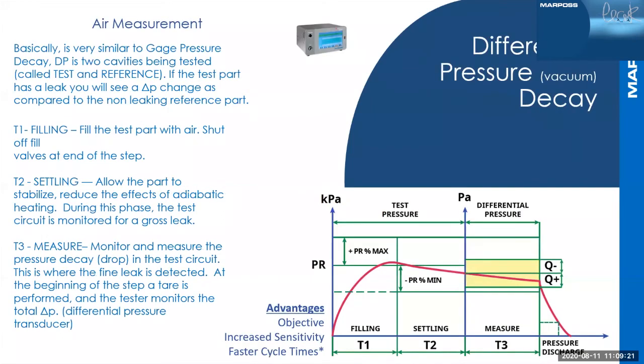The second pressure decay method is differential pressure decay. You'll notice in the graph the same 3 steps: fill, settle, and measure. The difference in differential pressure decay is we add a second reference volume circuit that is tested alongside the test part circuit. So we can also add a more sensitive pressure transducer that monitors for a difference between the reference volume and the test part. This allows for faster cycle times on large volumes with smaller leak rates.